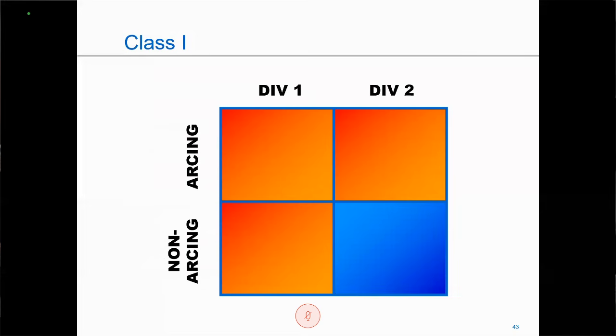And what we're saying is that in my Division 1 area, my gases are normally present. My arcing source, we're going to call it the combination motor starter. If that motor starter operates, my gases are present and explosions, so I need that explosion-proof equipment. Now, remaining in my Division 1 area with my gas and vapors present, my non-arcing source, a box. Here, one fault condition, I can have an explosion. So I need to have explosion-proof equipment.